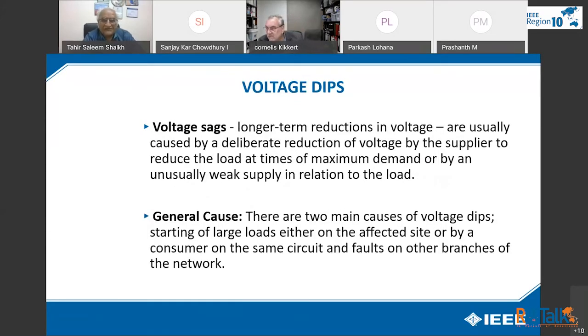Voltage sags, a longer-term reduction in voltage, are usually caused by a deliberate reduction of voltage by the supplier to reduce the load at times of maximum demand, or by an unusually weak supply in relation to the load, because of load shedding. What we call it is load shedding. There are two main causes of voltage dips: starting of large loads, either on the affected site or by a consumer on the same circuit, and faults on other branches of the network.